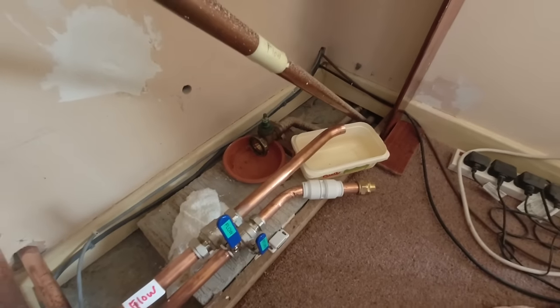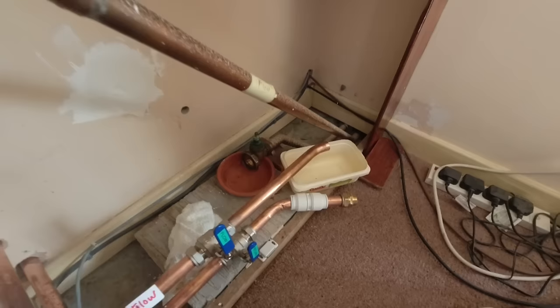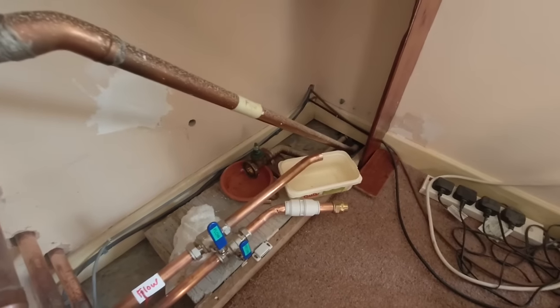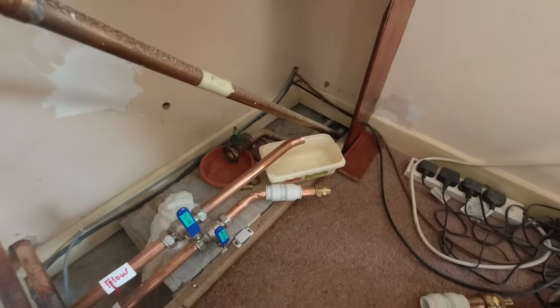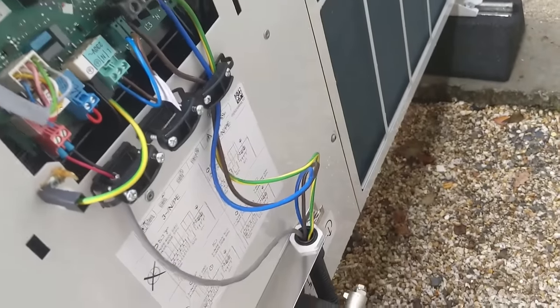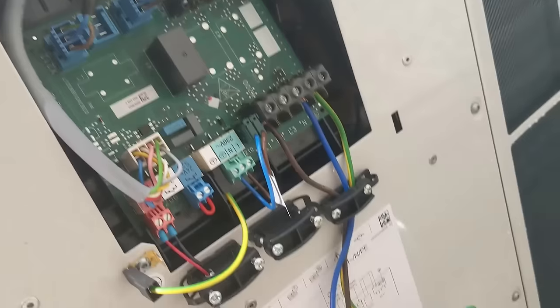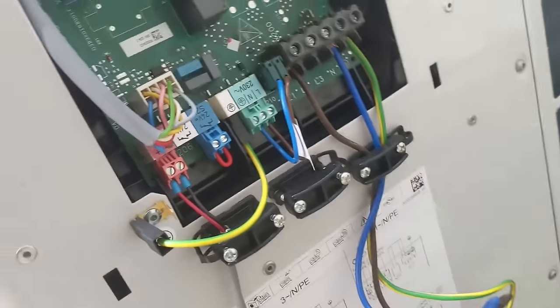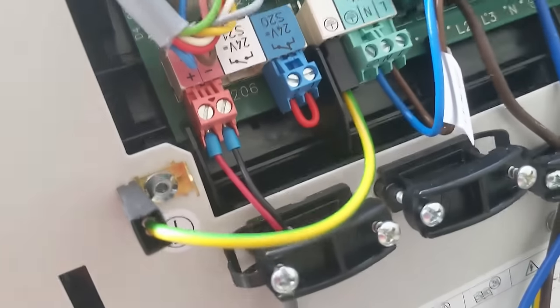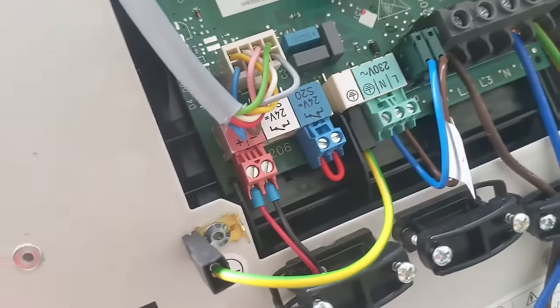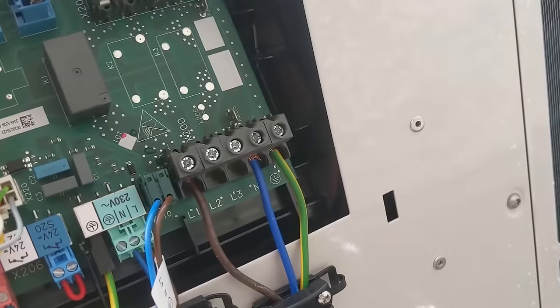So at least we can have hot water from the heat pump while I mess around with upgrading a few more radiators and flushing through the old system. Just doing the final connections here. This is what the inside under the back cover of a Vaillant aroTHERM looks like.